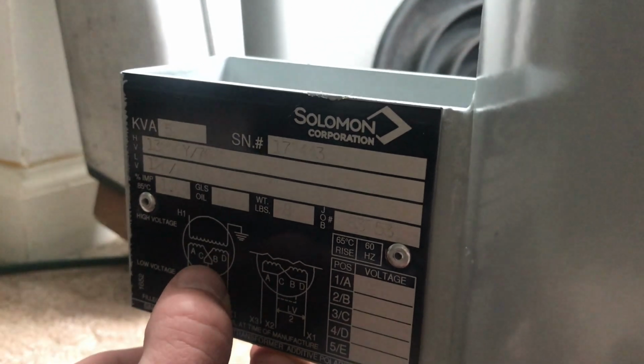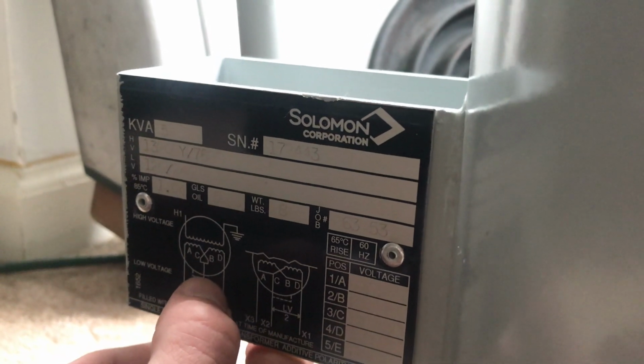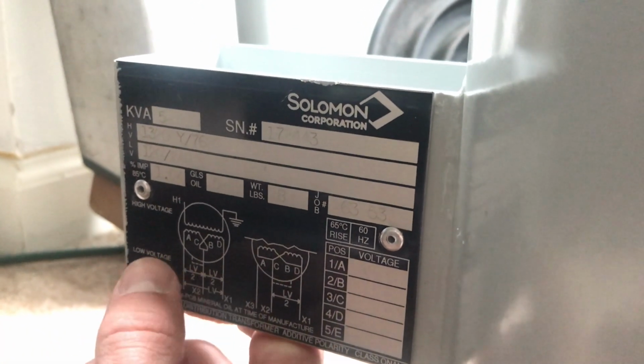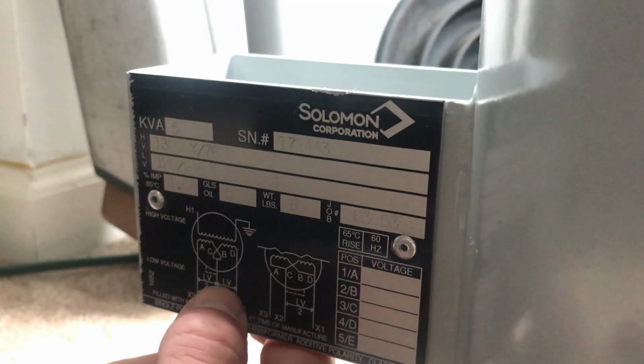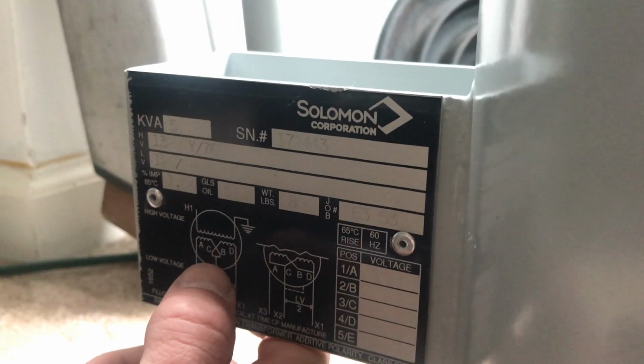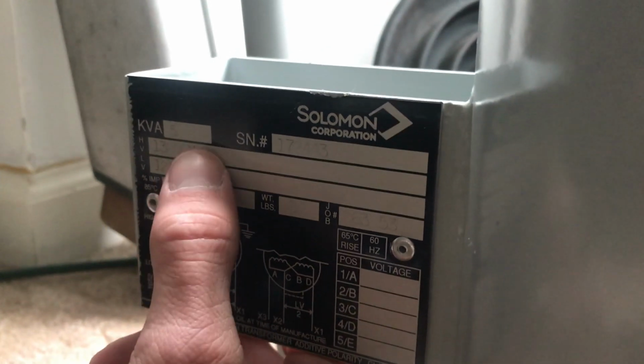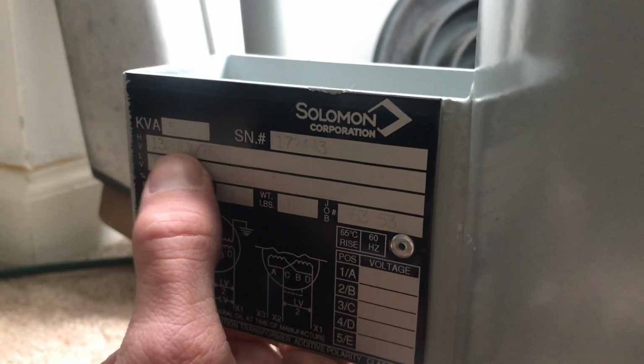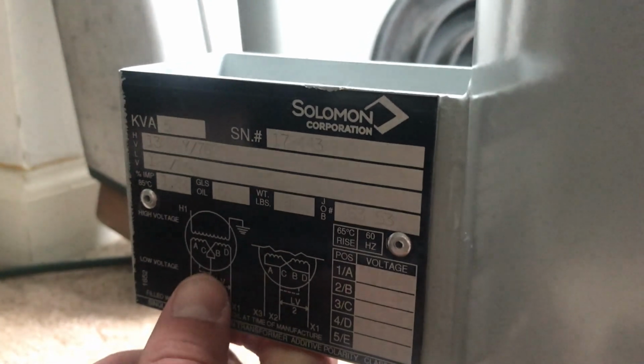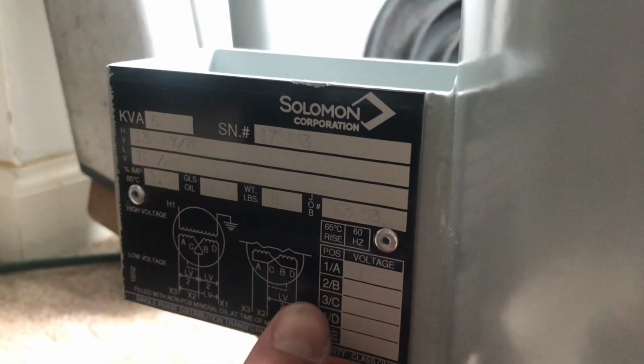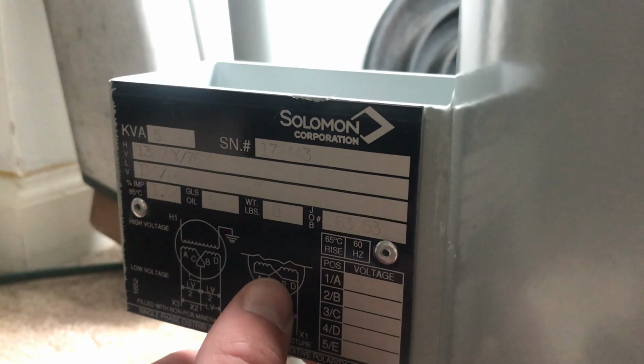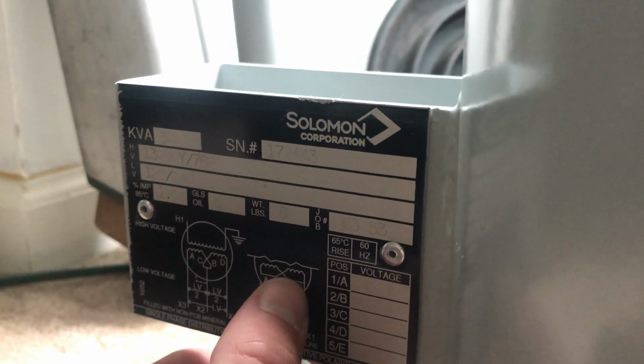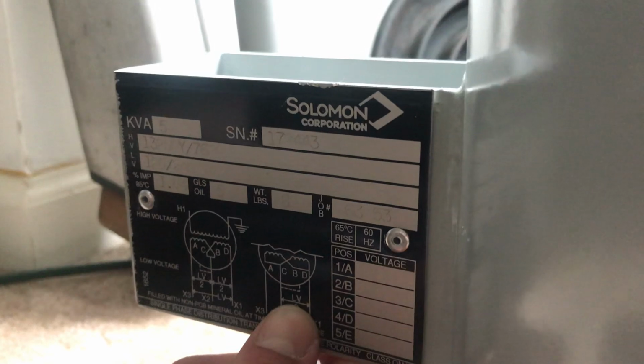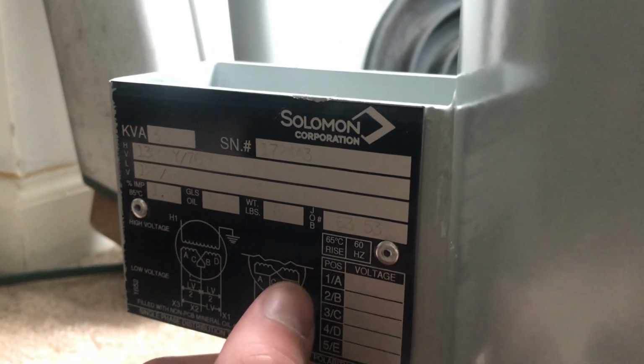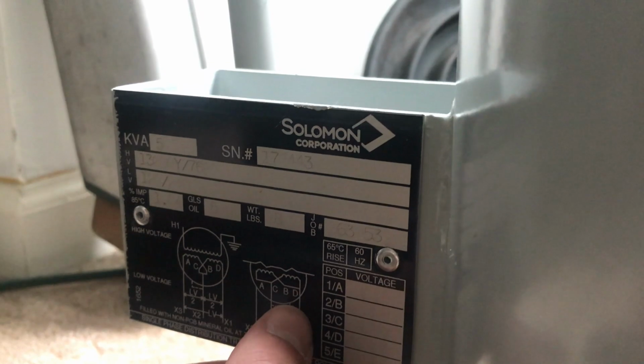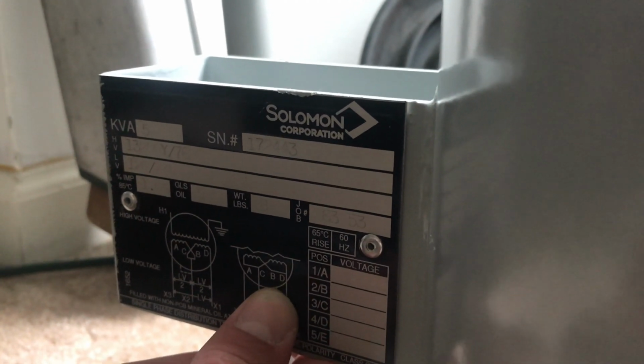In this factory configuration it is shown as a series connection, so you have 1, 2, and 3 outputs, 120 and 120, and the center one is always tied to ground on a Y transformer. So it's a 13200 grounded Y, so that's always tied to neutral ground. There's also a second configuration where you can parallel the 2 low voltage windings just to get 120 volts out. Utility companies do this a lot with 120/208 Y systems.